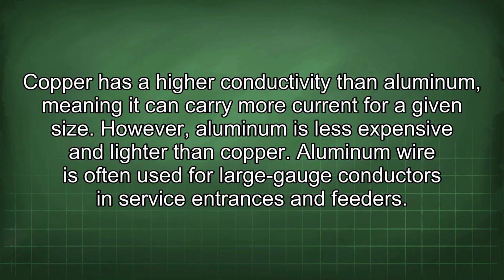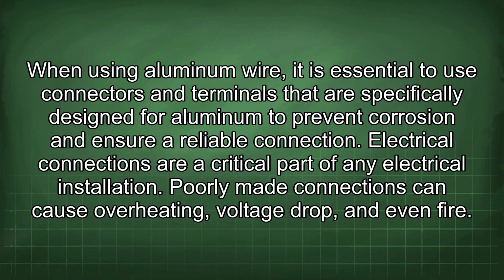However, aluminum is less expensive and lighter than copper. Aluminum wire is often used for large-gauge conductors in service entrances and feeders. When using aluminum wire, it is essential to use connectors and terminals that are specifically designed for aluminum to prevent corrosion and ensure reliable connection.